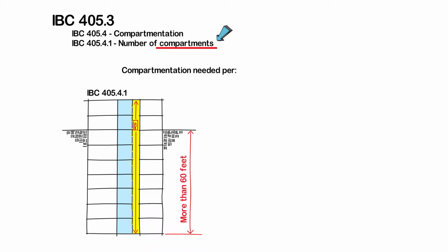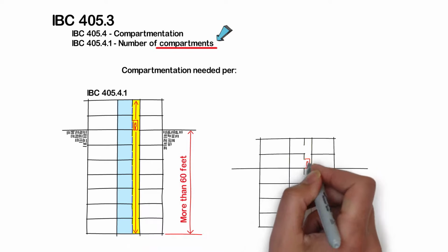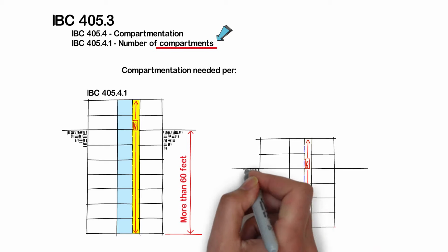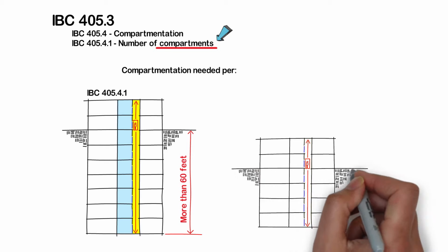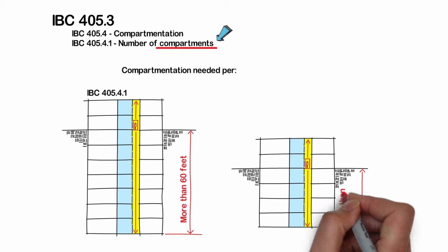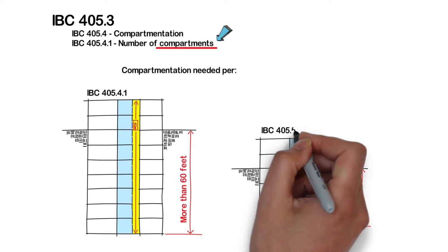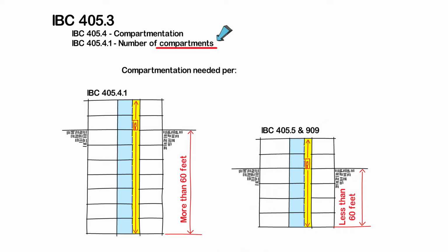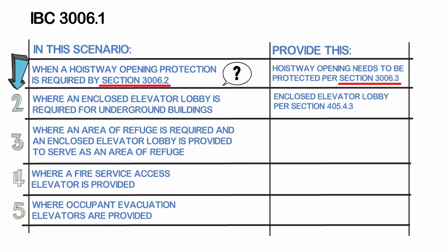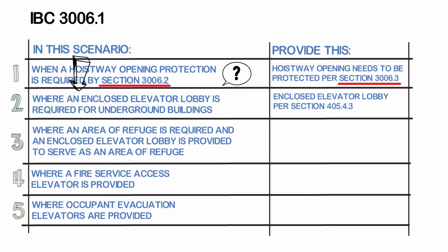However, I am not going to get into the details of this because it may get too complicated, but have in mind that even if an underground building did not have a floor level more than 60 feet below the finished floor level or lowest level of exit discharge, you might still need compartmentation because section 405.5 and 909 would require smoke control anyway.